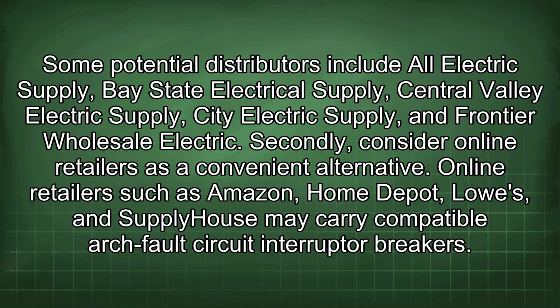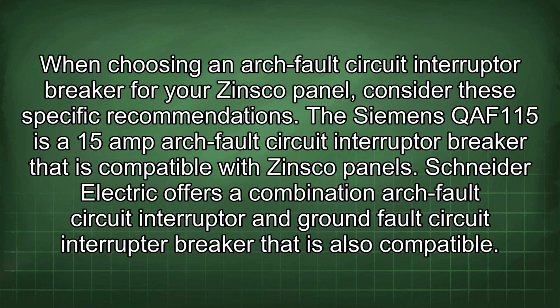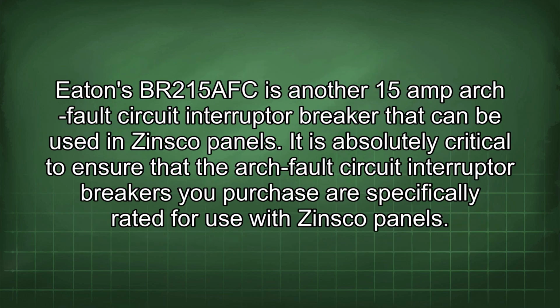Online retailers such as Amazon, Home Depot, Lowe's, and Supply House may carry compatible arch fault circuit interrupter breakers. When choosing an arch fault circuit interrupter breaker for your Zinsco panel, consider these specific recommendations. The Siemens QAF115 is a 15 amp arch fault circuit interrupter breaker that is compatible with Zinsco panels. Schneider Electric offers a combination arch fault circuit interrupter and ground fault circuit interrupter breaker that is also compatible. Eaton's BR215 AFCI is another 15 amp arch fault circuit interrupter breaker that can be used in Zinsco panels.